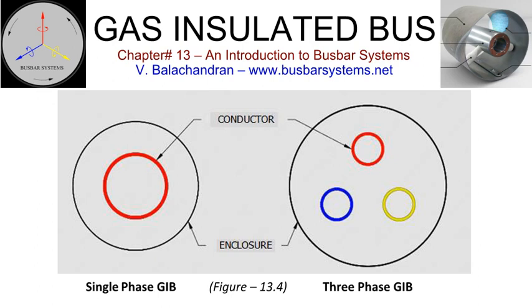Each insulator location is a potential cause of failure. For long route lengths, a spare single-phase GIB can be installed as a standby, for more than one set, in the event of an outage on any one of the phases. The gas-insulated bus can be classified under the 2 following categories. An active gas-insulated bus that has a disconnecting and grounding switch in the gas compartment. A passive gas-insulated bus that does not have any moving or switching device in the same gas compartment.